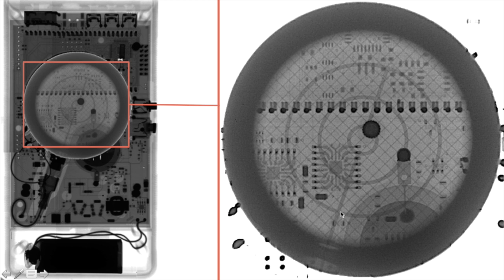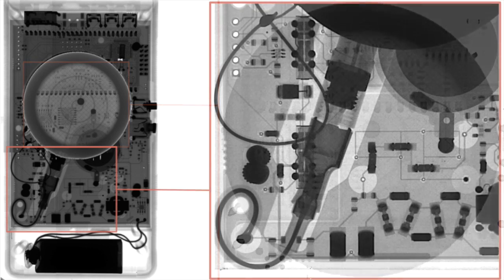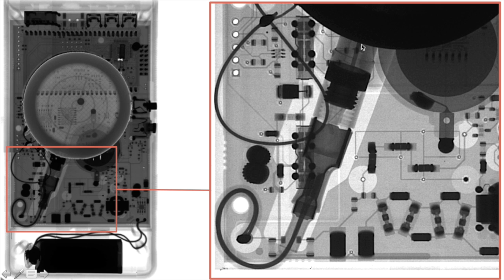You can see how that then goes through inside the cathode to the outside of the GM tube. That's the continuation of the anode, going through this wire that then connects to the high voltage circuit. And the cathode goes on the other side. These are selection switches on the top that we saw before. And this disc here is the buzzer, basically the beep for the unit.